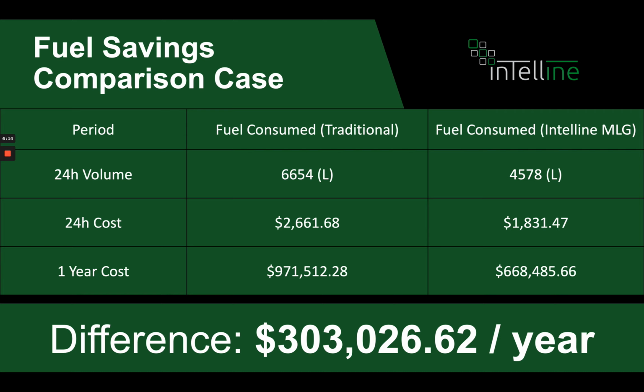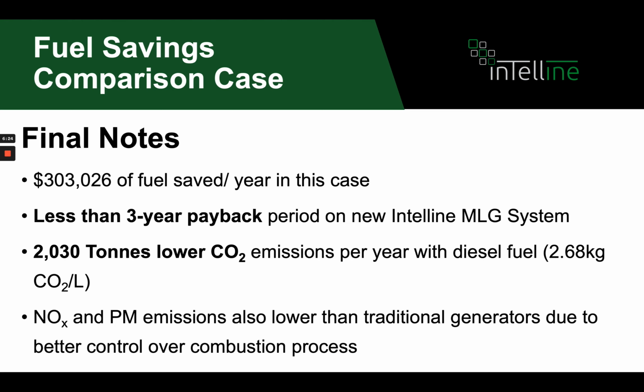This is a daily cost difference of $830, and over the course of a year, the fuel savings would total a whopping $303,000. In addition to the financial savings of burning less fuel, the MLG would also produce 2,030 tons less CO2 than the traditional generator per year, and the greater degree of control over the combustion process also substantially reduces the nasty NOx and soot emissions.